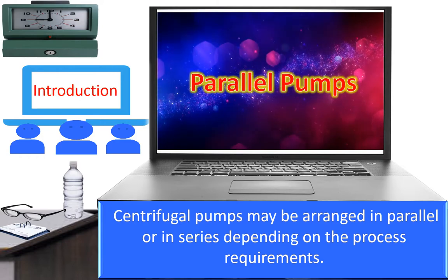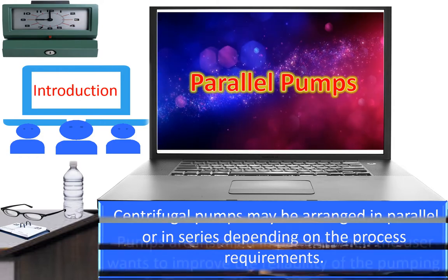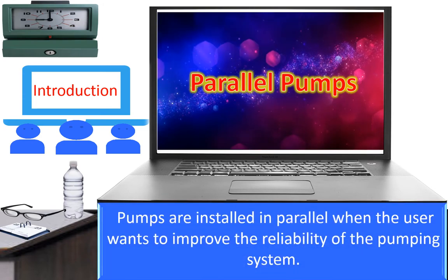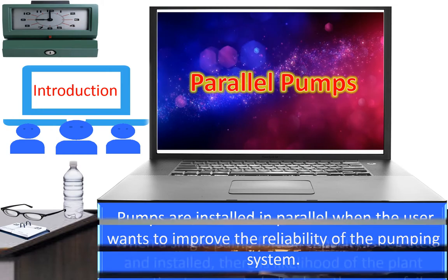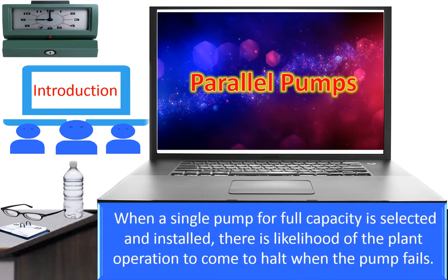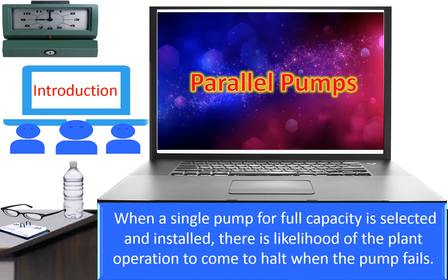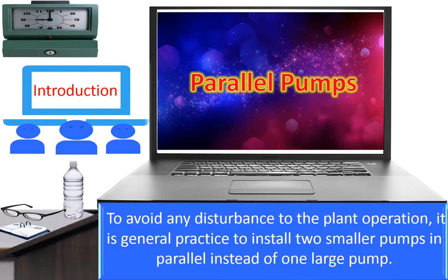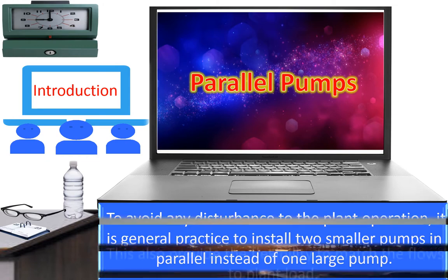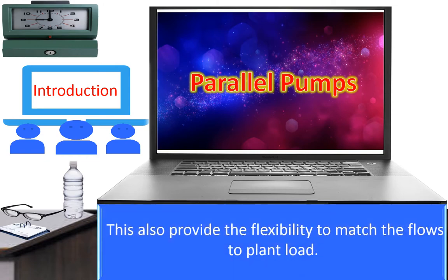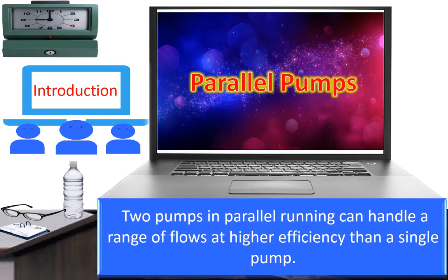Parallel pumps: Centrifugal pumps may be arranged in parallel or in series depending on the process requirements. Pumps are installed in parallel when the user wants to improve the reliability of the pumping system. When a single pump for the full capacity is selected and installed, there is likelihood of the plant operation to come to halt when the pump fails. To avoid any disturbance to the plant operation, it is general practice to install two smaller pumps in parallel instead of one large pump. This also provides the flexibility to match the flows to the plant load. Two pumps in parallel running can handle a range of flows at higher efficiency than a single pump.